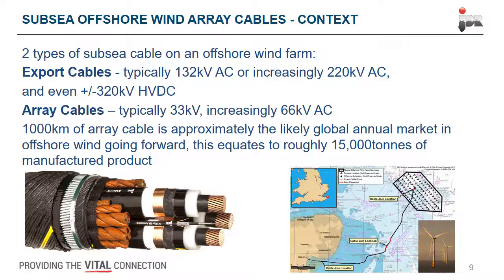If you went back a couple of years ago, almost all these export cables, including this one, would be 132 kV. But now, as wind farms have got larger, we're seeing increasingly 220 kV export cables. And some, which is definitely the trend for the future, are now moving to HVDC, typically plus or minus 320 kV.